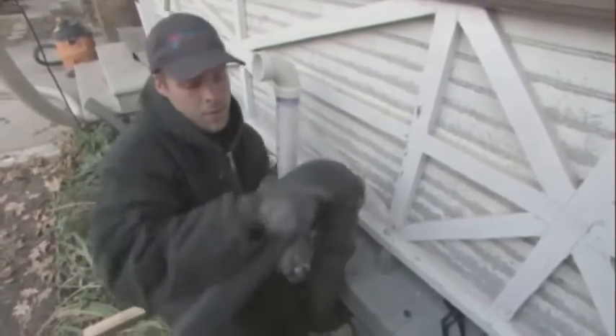Another issue we're also having with the vent piping is it's supposed to be insulated. These pipes do condensate. So we've got to run insulation from the wall underneath the deck all the way to these vents. The way it is now, it'll freeze. It does condensate, it'll freeze, block off your exhaust or your fresh air, and hence turn your furnace off. So you'll be left with no heat.